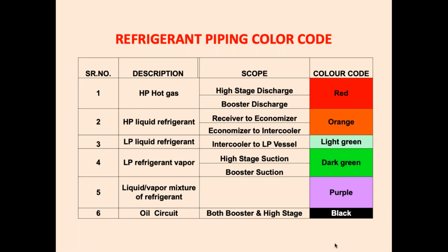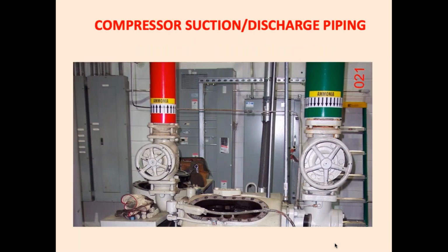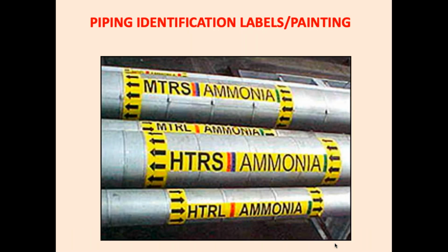I will not read this. You can see these colors: red, green, purple, black, etc. And then your identification of piping becomes easier. So look at this. This is a good piping. The ammonia discharge, red color with arrows and a sticker showing ammonia. The suction line green, showing again the direction of flow on the compressor side. So this is compressor suction discharge line pipe.